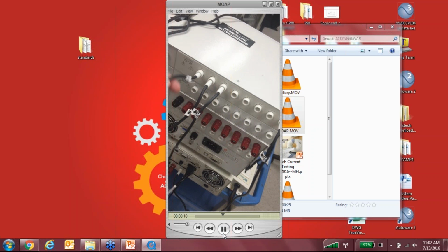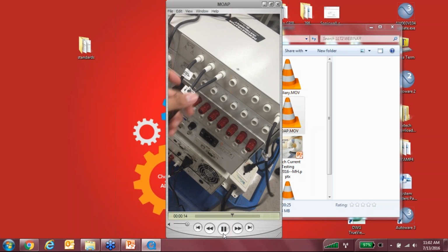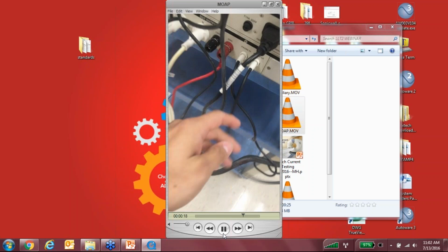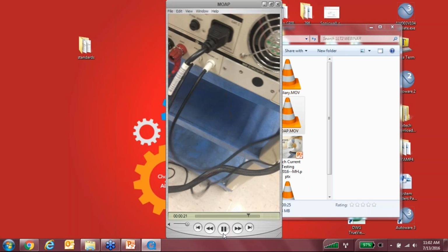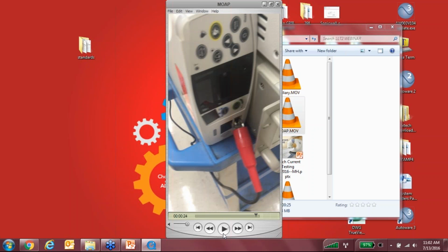And the other side of your MD, do you remember what that was? That was your applied part. So I still have that probe high going straight to the applied part of the medical device. So it's not that complicated if you know what you're doing.